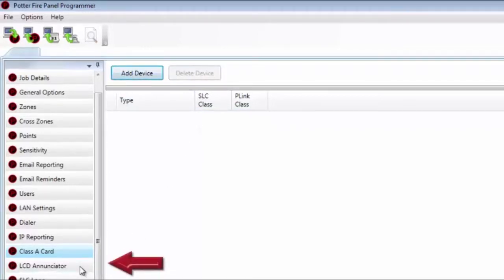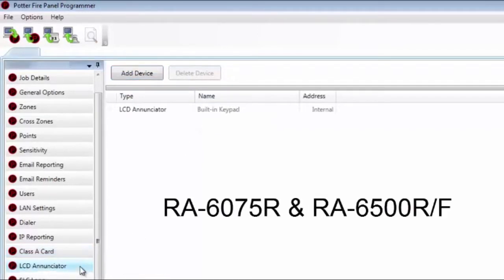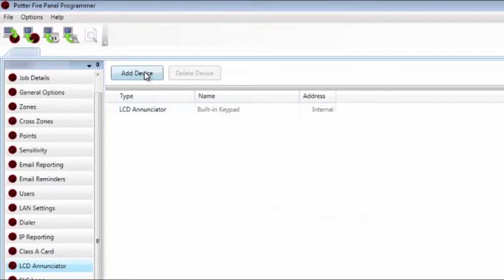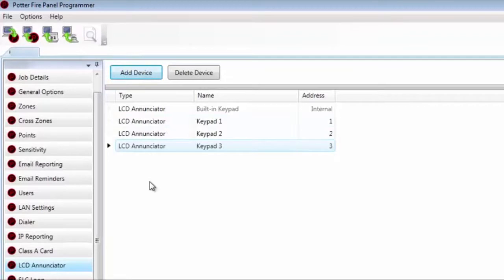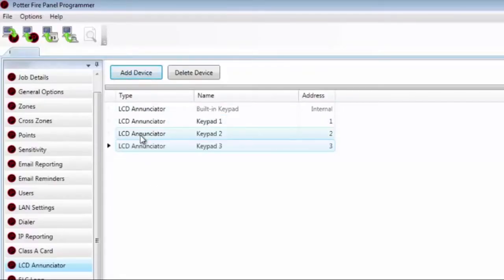Moving to the LCD annunciator — this refers to the RA-6075R and the RA-6500R or F. You can have up to 31 of these installed on the system. Click Add Device to add LCD annunciators. If you had run a Learn and had these installed in the field, they would already be in your program. The software does not distinguish between the small and large annunciator — the panels don't know the difference, so they are interchangeable.